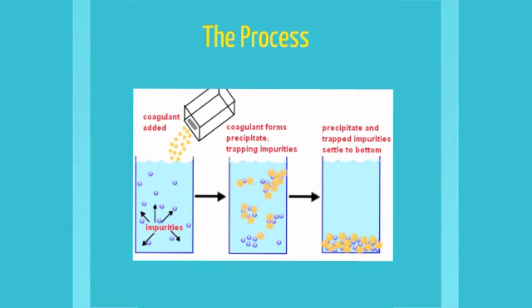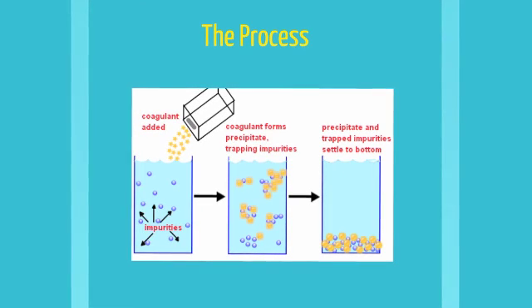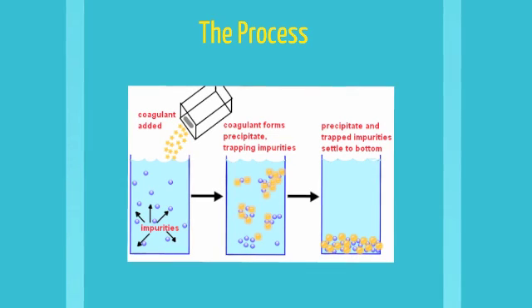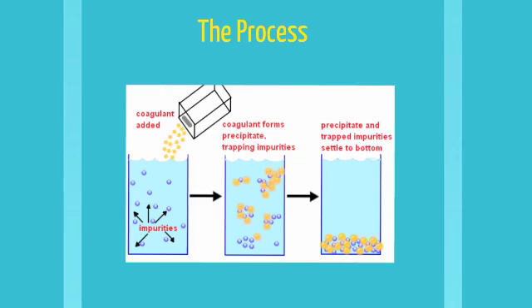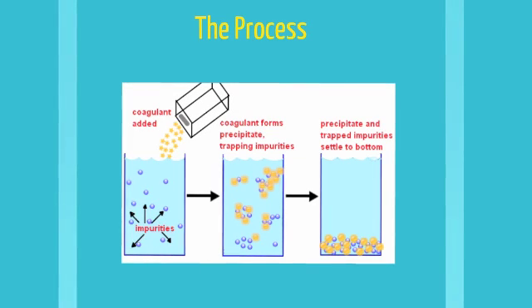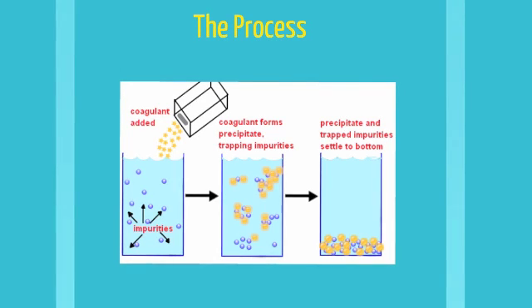Here is how the process of coagulation and flocculation works. First, the coagulant is added — remember, this is usually alum. After the coagulant is mixed with turbid water, the suspended particles come together to form larger particles called flocs. These flocs then settle down to the bottom, which leaves the water clear.